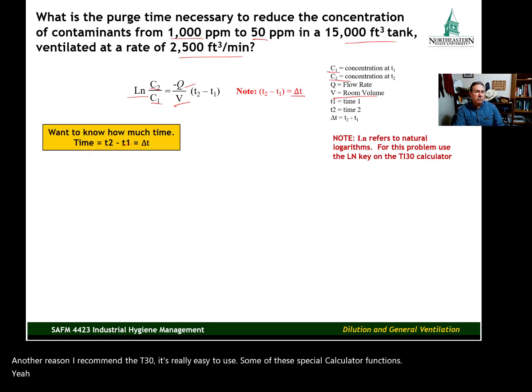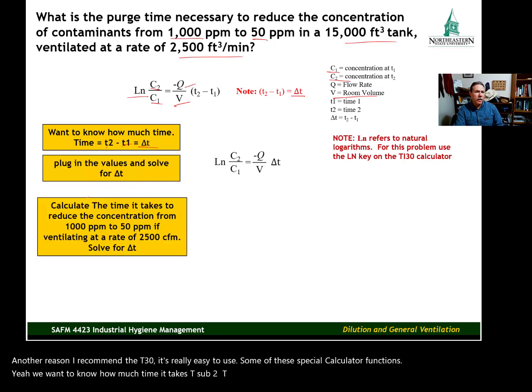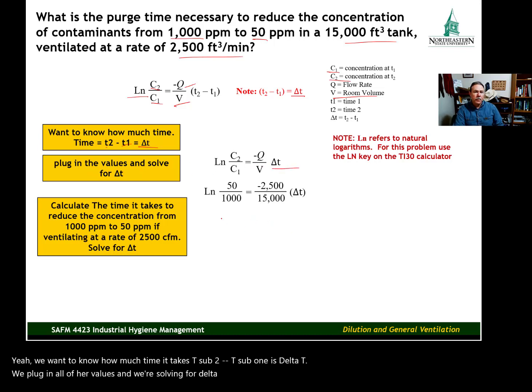We want to know how much time it takes. T sub 2 minus T sub 1 is delta T. We plug in all of our values and we're solving for delta T. Again, C sub 2 is 50 parts per million, concentration at time 2. Concentration when we begin at time 1, when we start the ventilation, that's 1,000 parts per million. Our ventilation rate is 2,500 cubic feet per minute, Q. Then the volume of the space is 15,000 cubic feet, and that's V. And now we just need to solve for delta T.